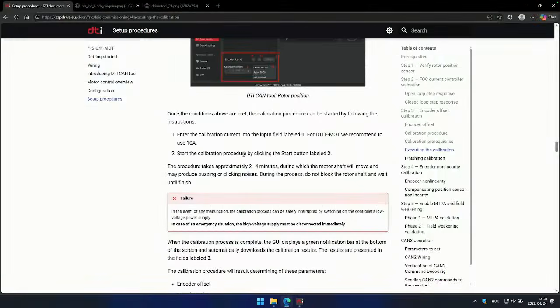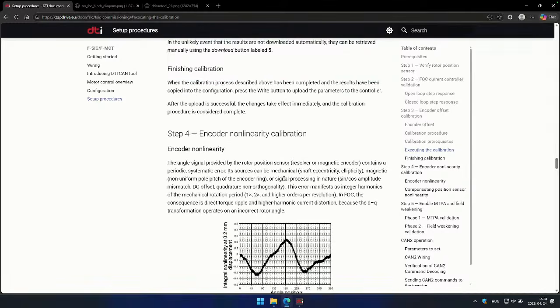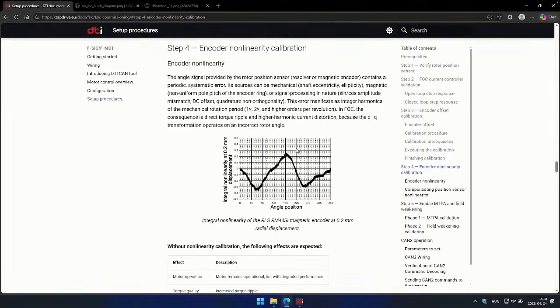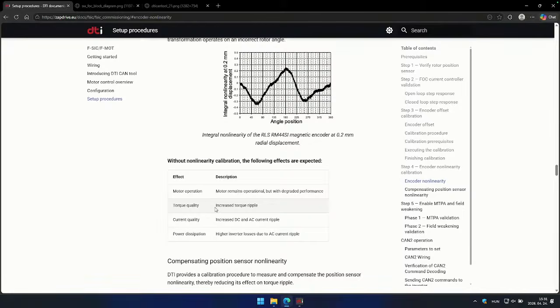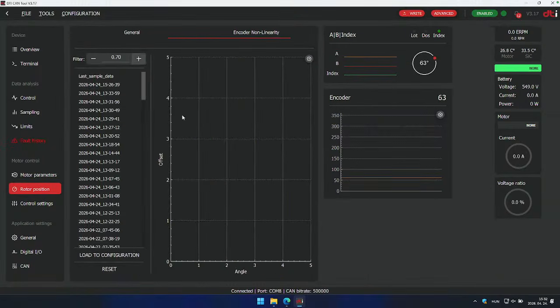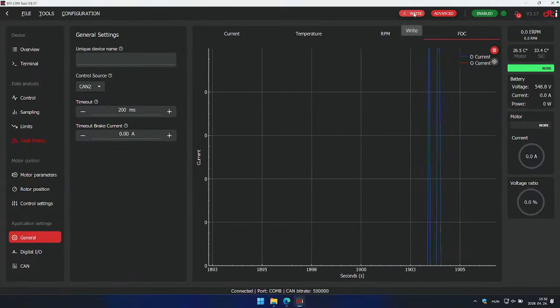Okay, good. The next thing we have to do right now is the encoder nonlinearity calibration. Why is it necessary? This is necessary because the rotor position sensor contains periodic systematic error, and it can be of a mechanical, magnetic or signal processing nature. So you have to do it to decrease the torque ripple, decrease the DC and AC current ripple, and in that way you can increase the motor control quality of your system. Right now you can do that here. We do not have any applied curve here, and I will just set the control source to CAN 2.